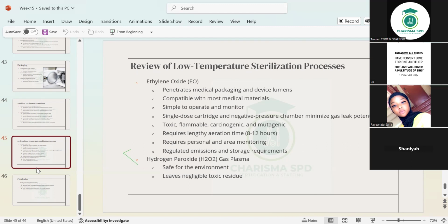All right, so look at it. This is just a review, and I want you to look at this slide very well. If you could take note of it. It's a summary of all three. All right? Then it tells you that the ETO requires lengthy aeration, 8 to 12 hours, for aeration to take place, okay, and requires personal and area monitoring. So looking at the time and everything, you could determine if you think your job needs to use this, depending on what instruments you're using and the IFU. The time is maybe going to be the last thing you consider. If it's your last option, you have no choice but to use it for low temperature sterilization. But that is not in your court. It's in your manager's court.